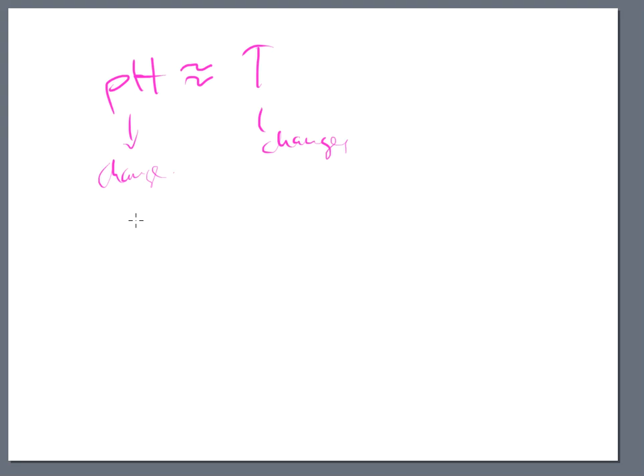A lot of the pH values we get in a laboratory are taken at whatever temperature the room is. So what if I'm working in a room that's super cold, 65 degrees, or very hot, up to 80 or 85 degrees? That's going to change my pH reading and the whole dynamic of how this operates. Maybe only slightly, but it will still change it.